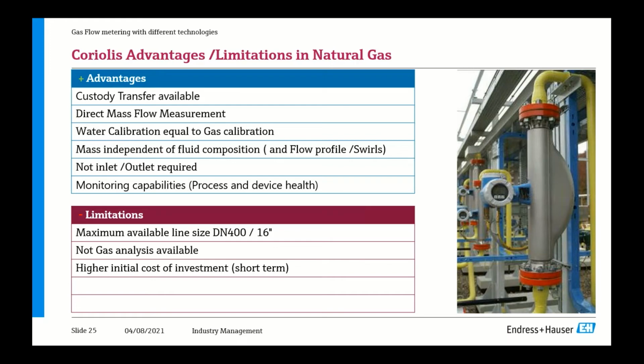Also, something very important to add is that some Endress+Hauser Coriolis meters have meter verification capabilities to allow the user to check the calibration of the meter, as well as the electronic sensors. The results from the meter verification procedures can be used according to AGA Report Number 11 to determine when a field or laboratory flow test should be completed. This has a significant benefit for the users because it will reduce the cost of field flow tests in gas applications.